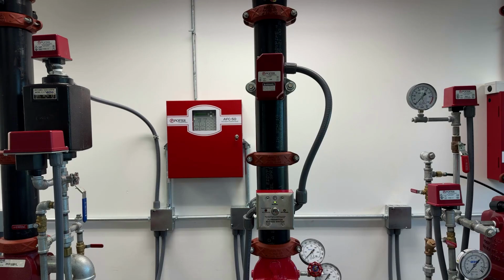The Flow Switch Bypass Switch, or FSBS, is a key-operated switch which, when turned to the bypass position, interrupts the alarm signal from the flow switch to the fire alarm control panel, allowing you to fill a system or perform maintenance without alerting central station monitoring or the fire department.